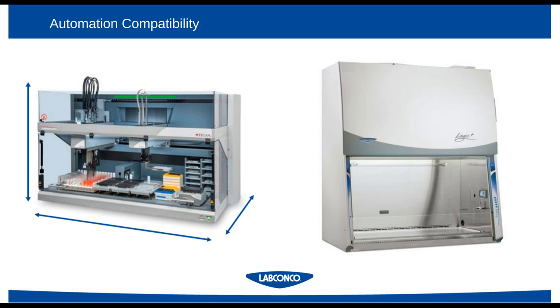Certainly, if you're a safety officer on this presentation, you've seen an overloaded fume hood or a biosafety cabinet, and that is one of the most disruptive practices to the airflow that ensures the product will function correctly. So as you compare the sizes, it's really important not just to look at the available dimensions inside the hood, but the available dimensions plus an envelope around the instrument to ensure good containment.